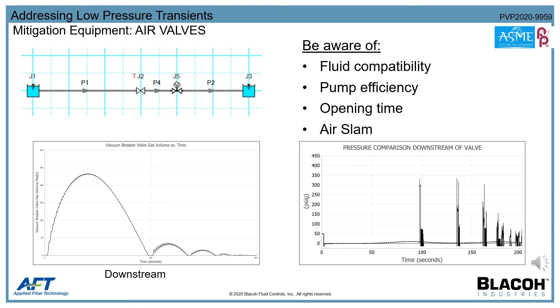The second challenge is pump efficiency, as air in the line can add unwanted loads on the pump. Third, it's important to consider the time it takes for the air valve to open — in the world of high-speed transient pressure waves, a tenth of a second matters. There are also many applications where air valves cannot be trusted to open due to fluid media and general clogging; in cases like these, you might even see redundant air valves placed side by side.